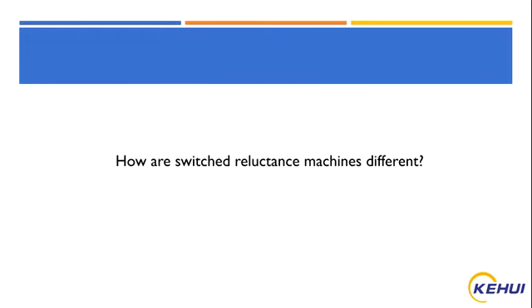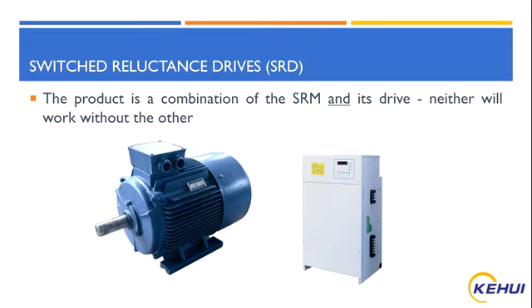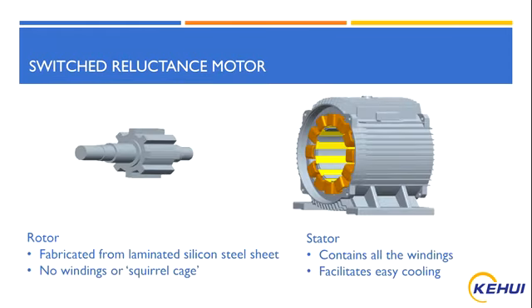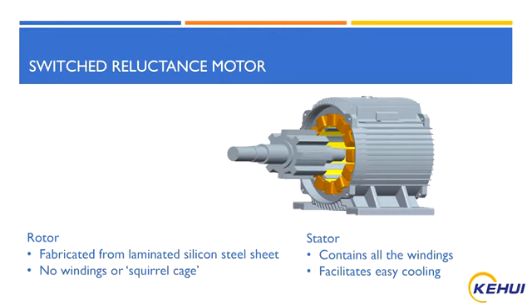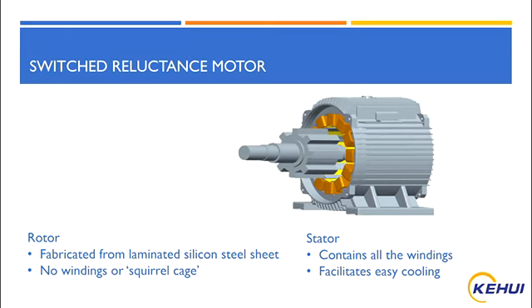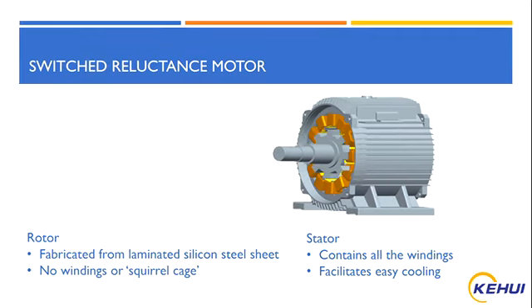But how are switched reluctance machines different? The product is a combination of the switched reluctance motor and its drive. Neither will work without the other. The switched reluctance motor has a simple, rugged structure. The rotor is simply made of laminated metal. There are no permanent magnets or windings, making it very reliable and relatively low cost. The design also features a solidly built stator with very simple windings, which allow for the high-speed operation of the motor.